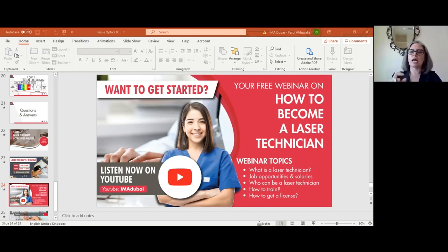Considering that I have a very, very short pulse duration here, with Candela my setting is a very aggressive setting. The company tried to compensate for this aggressive setting with cryogen, and in the market you will find so many patients, as I told you, who have very good results in terms of hair removal from the first session, but very big risks. A dark patient, skin type 4, so many get pigmentation.